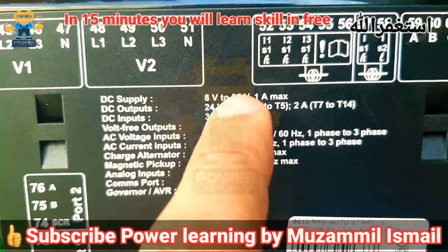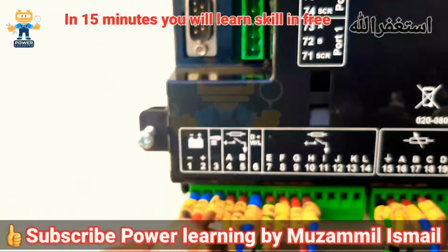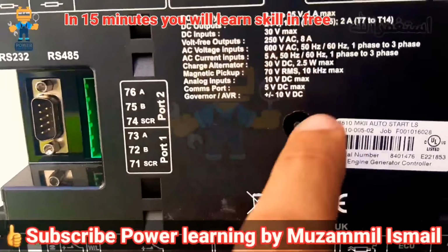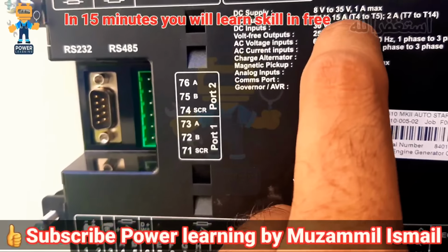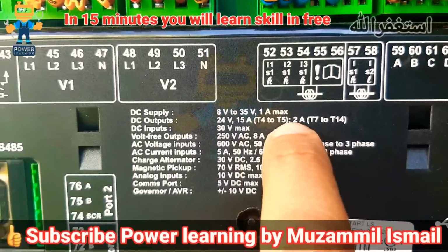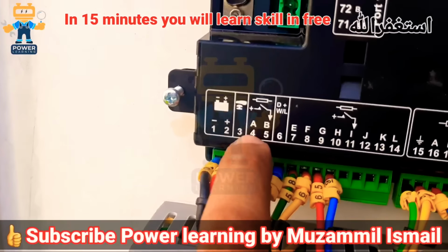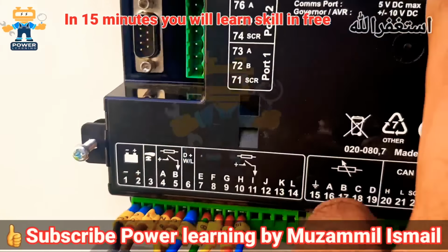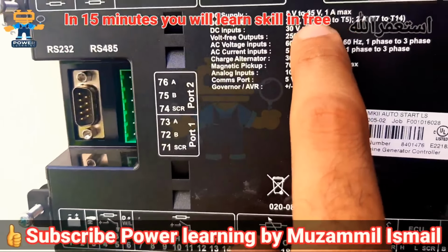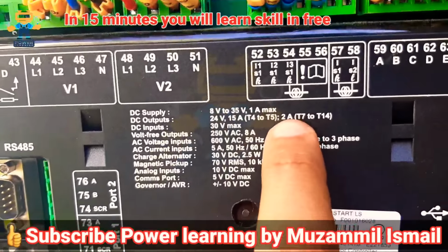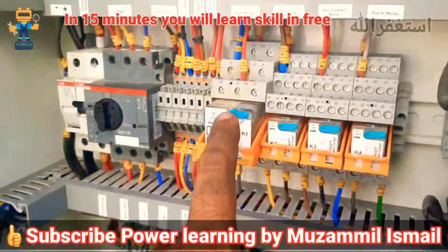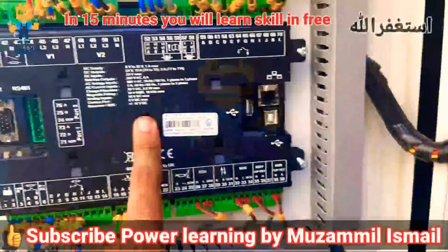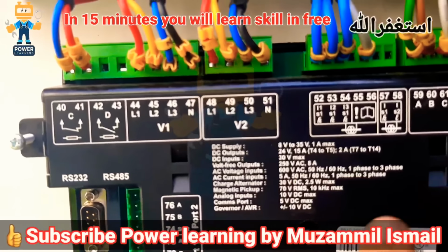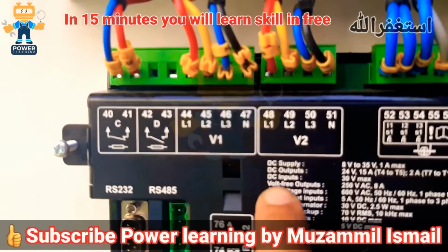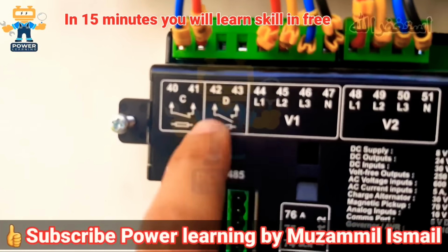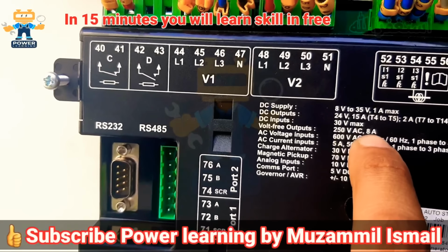Okay, a DC supply from 8 to 35 volt is required here to operate this controller. DC outputs, these are the DC outputs, 24 volt 15 ampere from terminal number 4 to terminal number 5. For example, this is terminal number 4 and this is 5. Only these two terminals have a 15 ampere contact rating, but from T7 to T14 we only have 2 ampere. So for this reason we are using external relays to protect our controller from any surge or any overload condition.